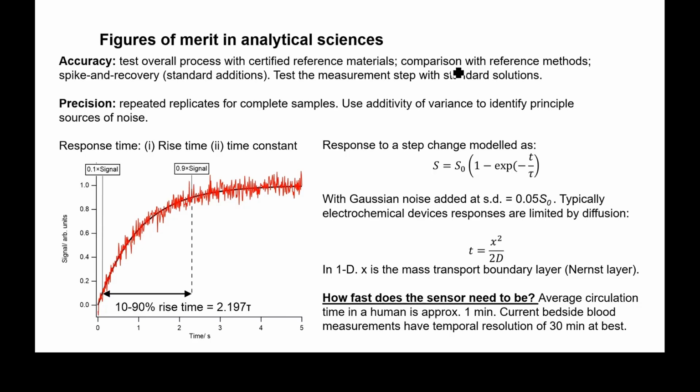So we ran our sensor data against a mass spec determination, because any source of error that would cause our biosensor data to deviate from the true or accepted value is unlikely to be the same source of error that would contribute to offset in a mass spectrometric method. So when we got good agreement between our mass spec data and our sensor data, we were greatly encouraged that the device was really working correctly. So that's a concrete example of why this is important. And to estimate the precision, you get a bunch of replicate samples, or you divide your sample up into multiple samples, and you do lots of repeats.